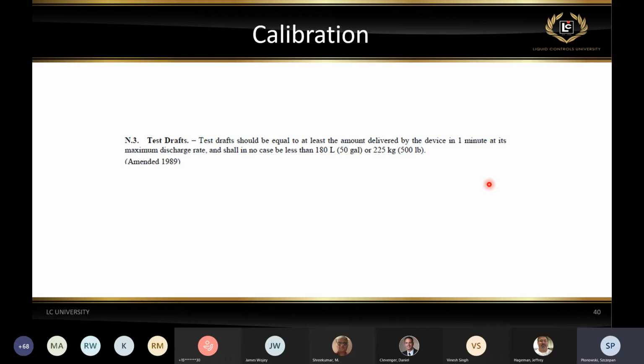We're seeing often that in the field, proving is done with much smaller devices, and generally that's going to create a lot of problems, not only from an accuracy but a repeatability standpoint, because most of the time you're not really running even a full flow of the meter when your prover size is 5 gallons and your discharge flow rate is 80 gallons a minute. There's no way of making it accurate.